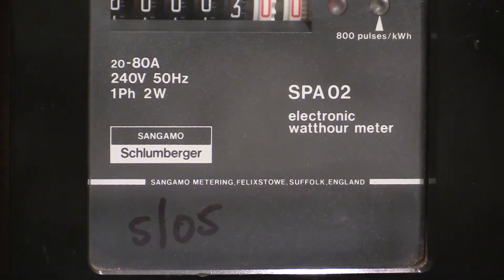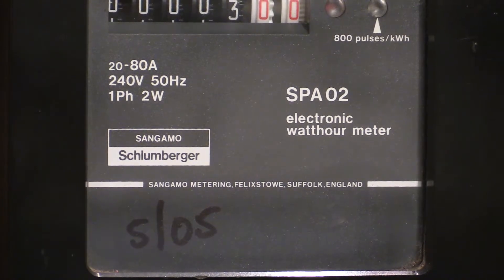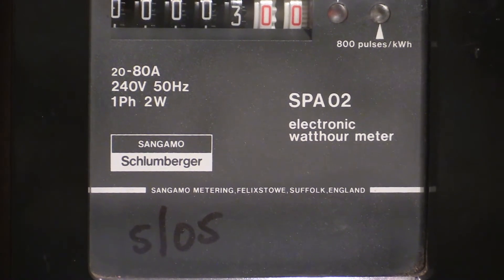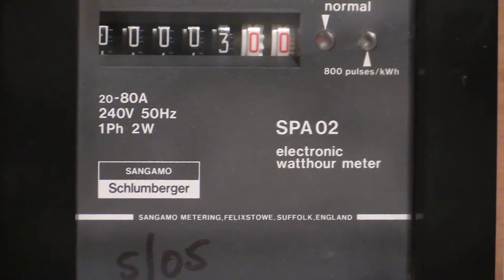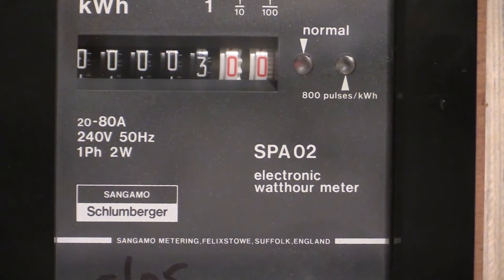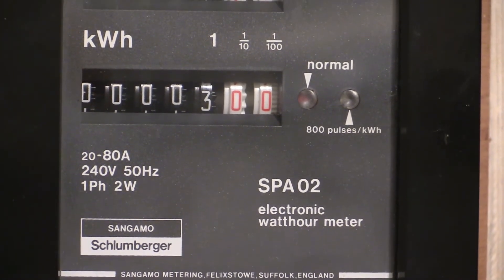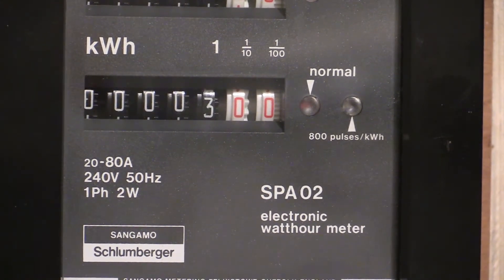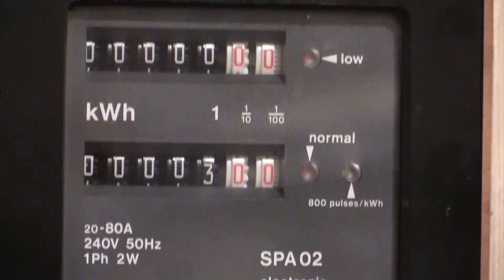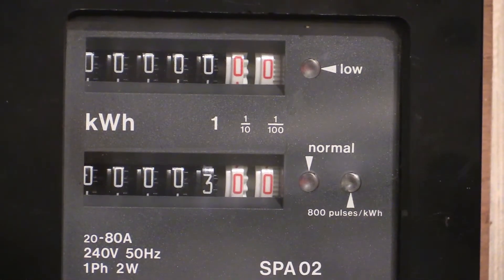Sangamo Metering, Felixstowe, Suffolk, England. SPA02 electronic watt-hour meter. 20 to 80 amps, 240 volts, 50 Hertz, one phase, two wire. 800 pulses per kilowatt hour for that right-hand light. The left-hand light indicates that the normal rate is active, and there's a low indicator light up there to indicate that the low rate is active.